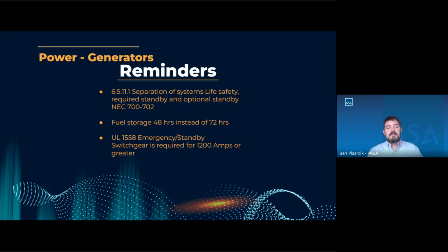Separation of life safety, required standby, and optional standby. This comes up quite often. We do have to have three separate transfer systems separating those loads, giving priority to those loads. Typically it is 10 seconds for life safety and then typically 60 seconds for the other two. And again, that gives the priority to the most important loads.